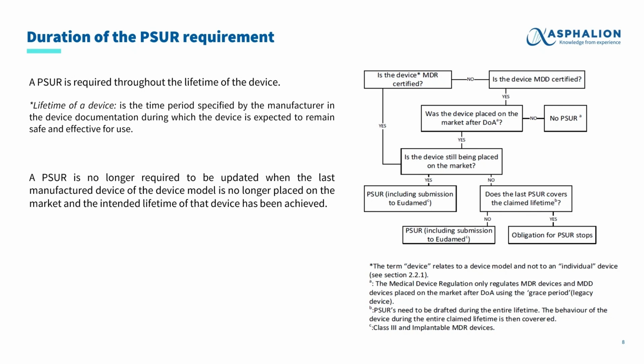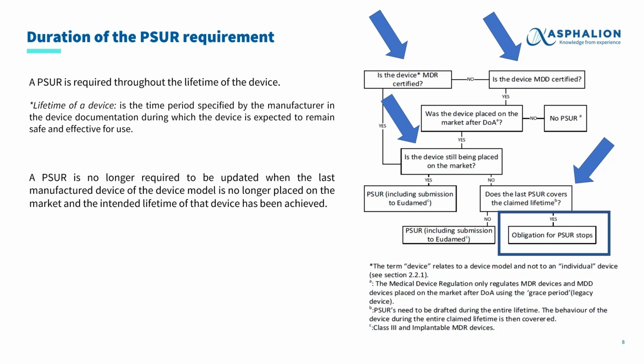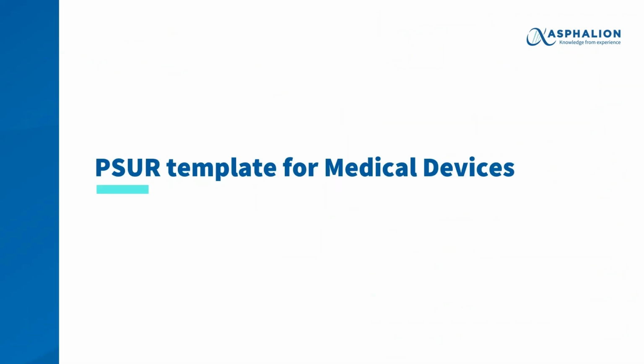been achieved. So, to understand it a little bit better, if we focus on the diagram on the right of the slide, if the medical device is certified under MDR or MDD and it's no longer placed on the market, we have to check if the previous PSURs have covered the entire lifetime of the medical device. Then, if the lifetime is covered, the obligation for PSUR preparation stops and the manufacturer doesn't have to present any PSUR for the medical device. Now, let's focus on the PSUR template proposed by the MDCG guidance, which can be useful for manufacturers when preparing their PSURs.